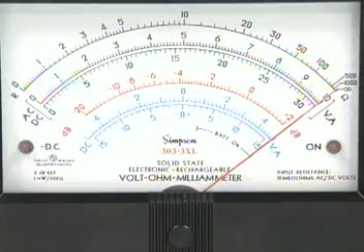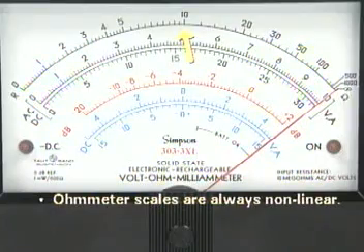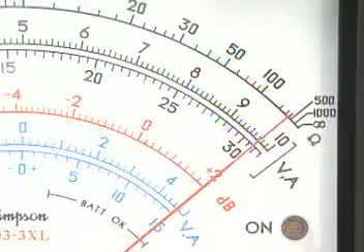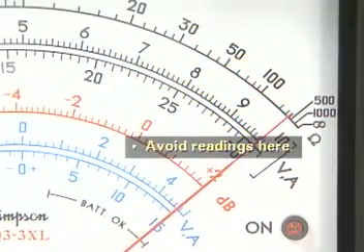Ohmmeter scales are almost always the top scale on a meter, and are always non-linear. The scale markings near zero are widely spaced. This is the scale area where most accurate readings are taken. The space between scale markings near infinity is narrow, showing the infinite progression of numbers. Readings here should be avoided.